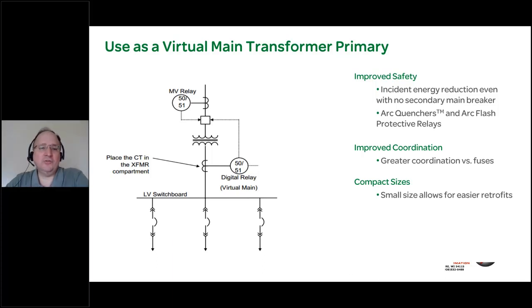On top of that, arc quenchers and of course active arc quencher protective relays are available in these hybrid configurations. And again, to be clear, if you or your customer is satisfied with 8 calories per centimeter squared or 4 calories per centimeter squared, you do not need to implement an arc quencher to achieve that. We can typically achieve that with zone selective interlocking and differential relaying in this equipment. But if you're in a critical power environment where you want to ensure the survivability of the asset itself and the downstream assets that are protected by the light sensor network, arc quenchers and active arc quenching, of course, we believe this represents the future of electrical system safety and reliability both in the United States and globally.